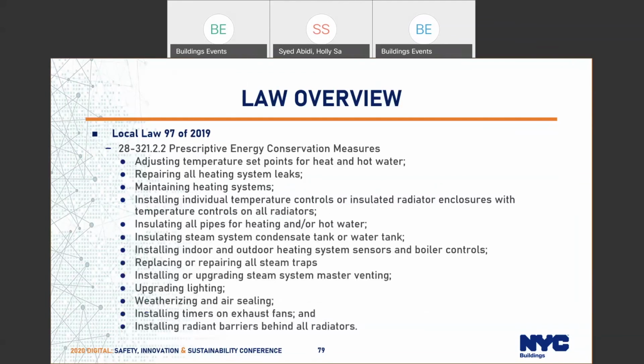So what are those prescriptive measures? They include adjusting temperature set points for heat and hot water, repairing all heating system leaks, maintaining heating systems, installing individual temperature controls or insulated radiator enclosures with temperature controls on all radiators, insulating all pipes for heating and/or hot water, insulating steam system condensate tanks or water tanks, installing indoor and outdoor heating system sensors and boiler controls, replacing or repairing all steam traps, installing or upgrading steam system master venting, upgrading lighting, weatherizing and air sealing, installing timers on exhaust fans, and installing radiant barriers behind all radiators.